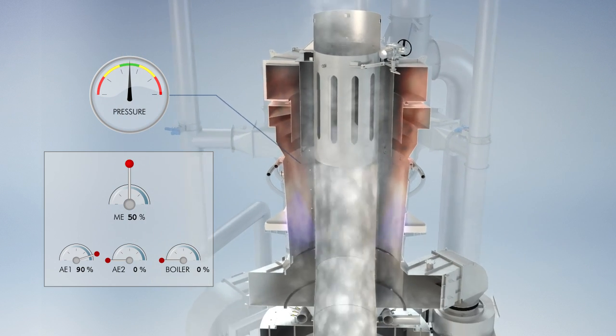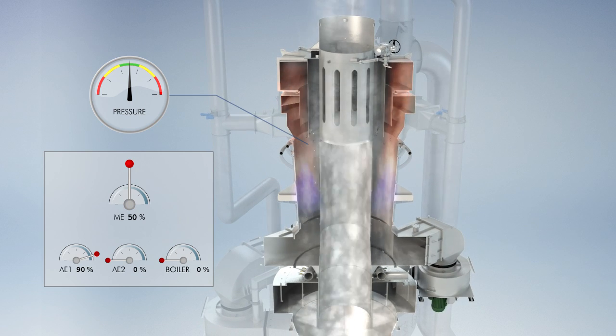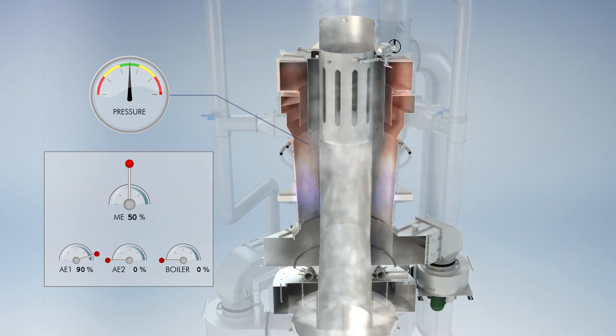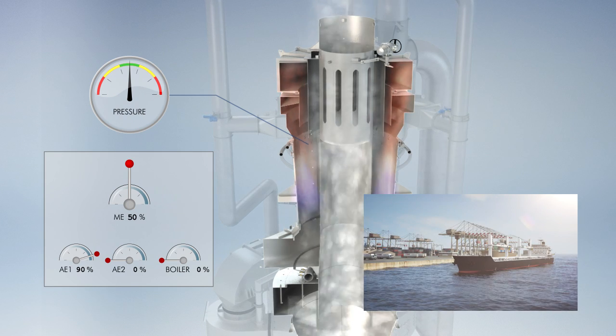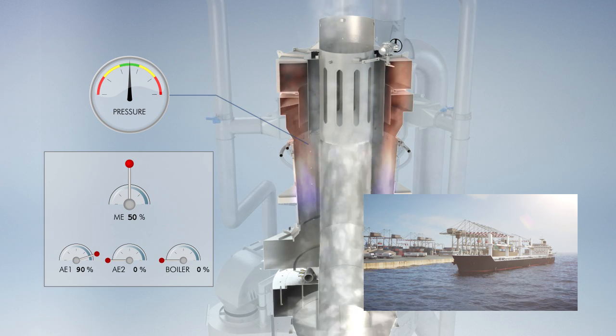Between 50 and 100% exhaust load, the fans operate at full speed. When the exhaust load falls, for instance when the vessel is in port, frequency drives will adjust the fan speed and water flow down to 50% to save on energy.